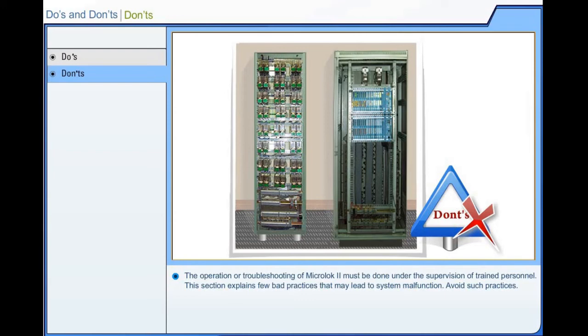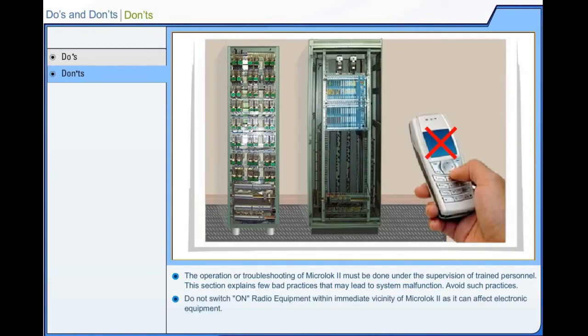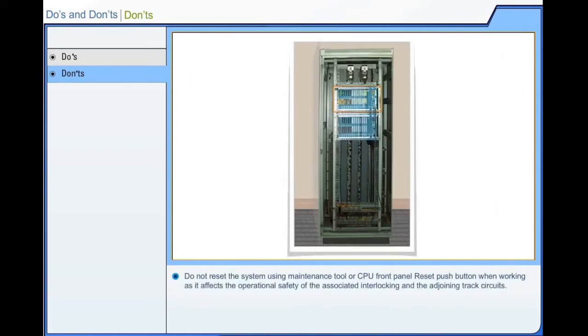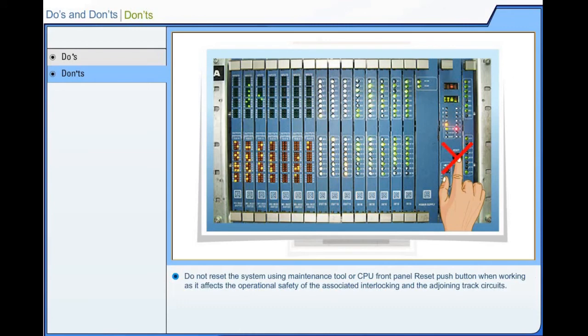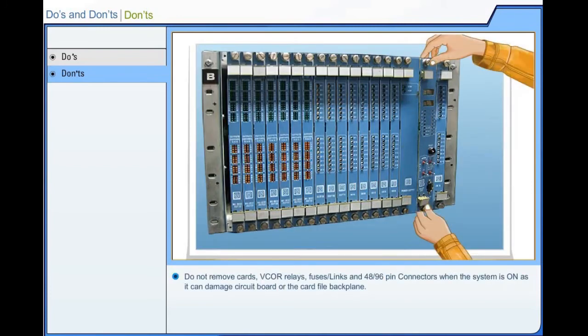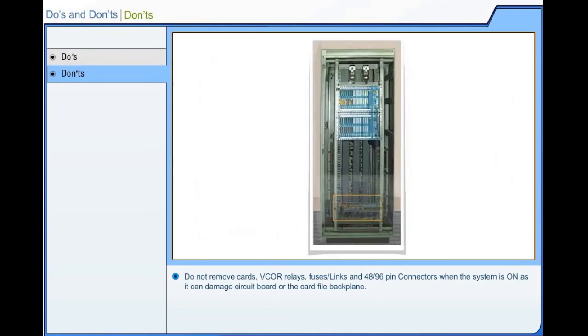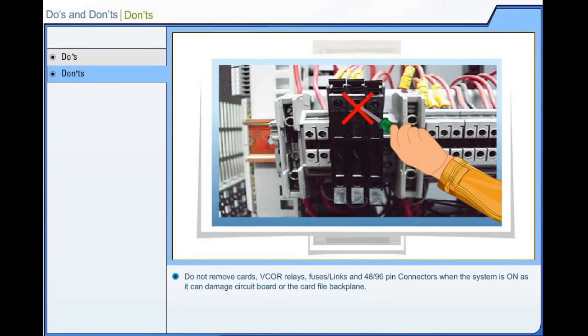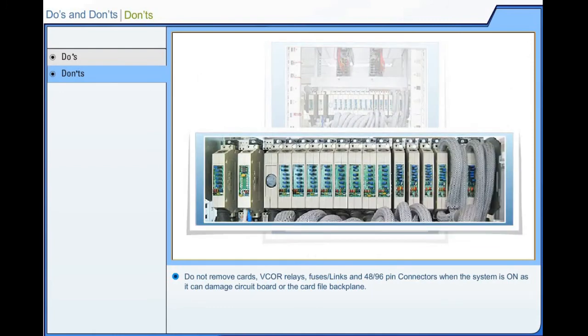Don'ts. This section explains a few bad practices that may lead to system malfunction. Avoid such practices. Do not switch on radio equipment within the vicinity of Microlok II as it can affect electronic equipment. Do not reset the system using the maintenance tool or the CPU front panel reset push button when working, as it affects the operational safety of the associated interlocking and the adjoining track circuits. Do not remove cards, vital cutoff relay, fuses, links and 48 and 96 pin connectors when the system is on, as it can damage the circuit board or the card file backplane.